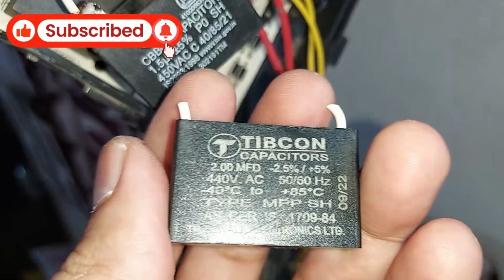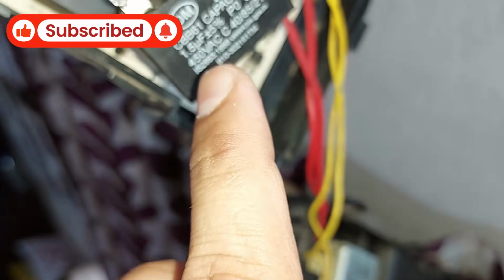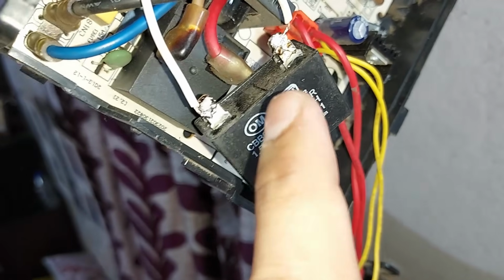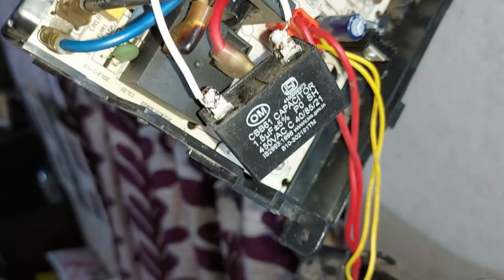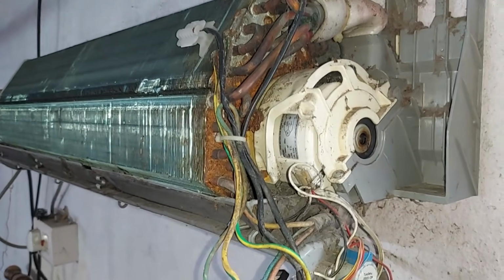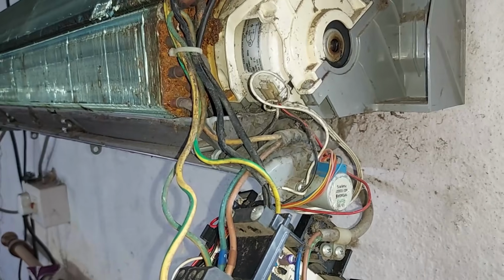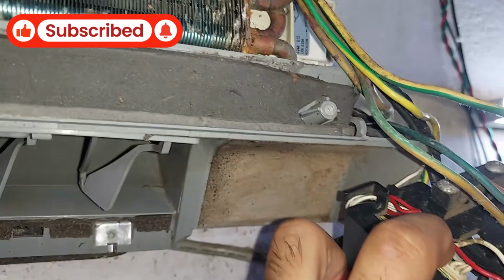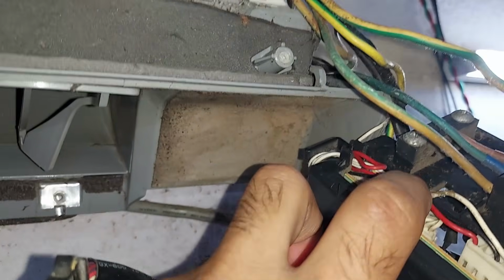So I used this one for 2 MFD. Now the original one, 1.5 MFD, and this capacitor looks much better than before. So now let's turn this AC on and check if the blower is working or not. All right, now let's turn this thing on from this PCB switch.